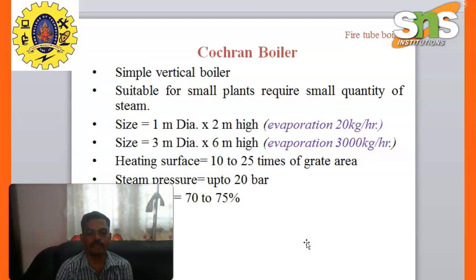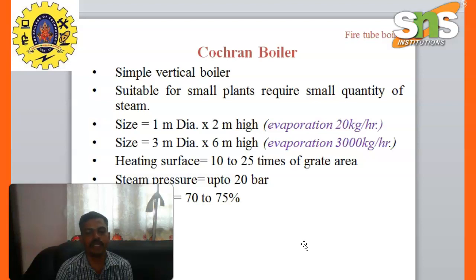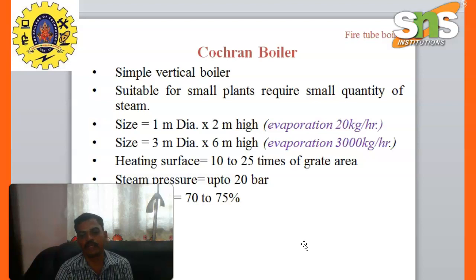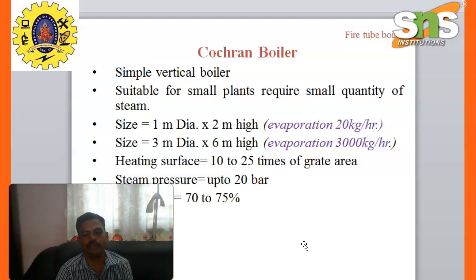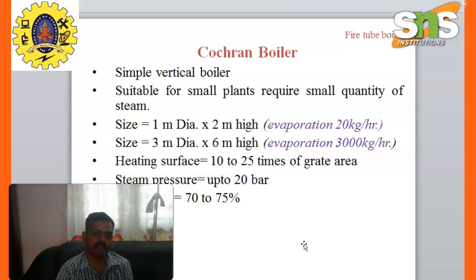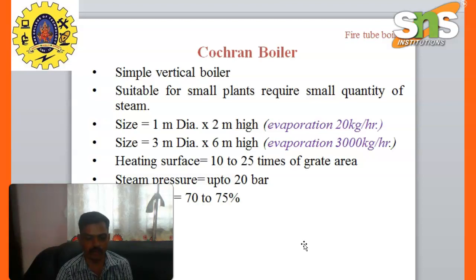Suitable for small plants requiring a small quantity of steam. The specification of the boiler: 1 meter diameter into 2 meter height, that means evaporation 20 kg per hour. Size 3 meter diameter into 6 meter height, that means the evaporation range is 3000 kg per hour. The heating surface is 10 to 25 times of grate area. The pressure of steam maximum up to 20 bar. The efficiency is 70 to 75%.